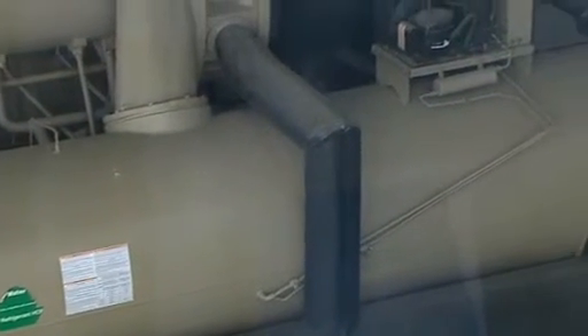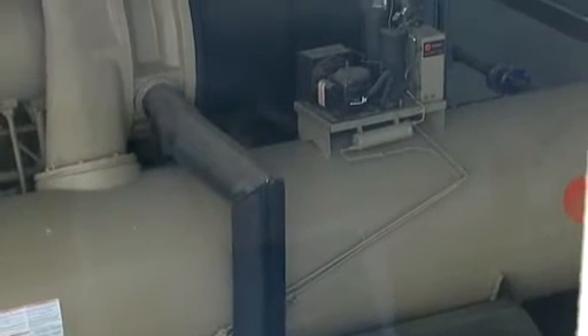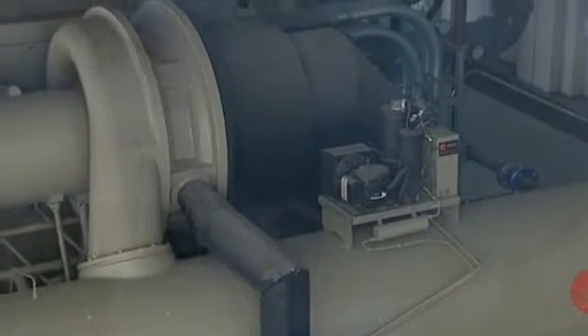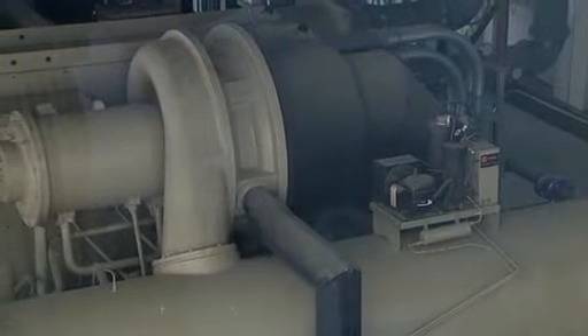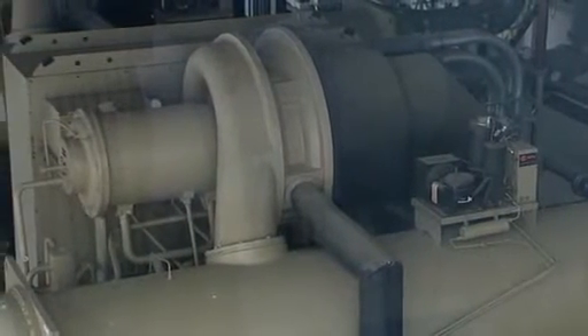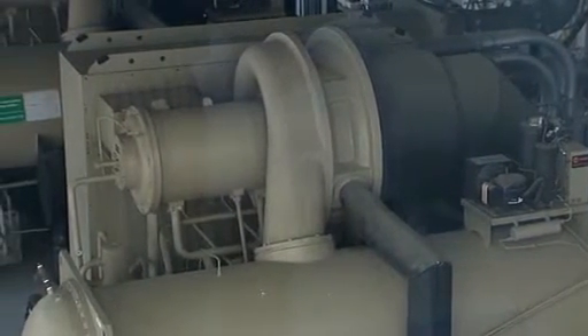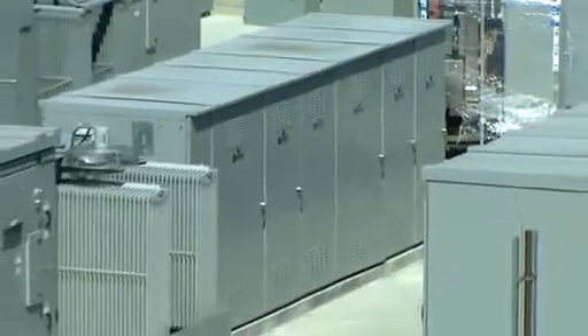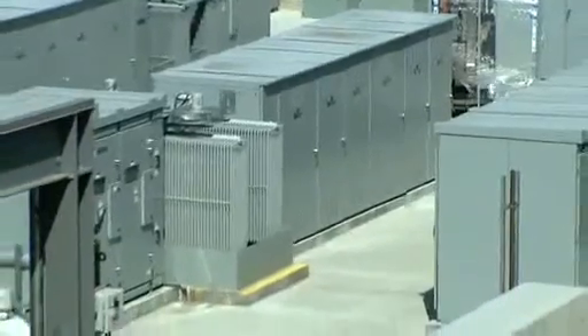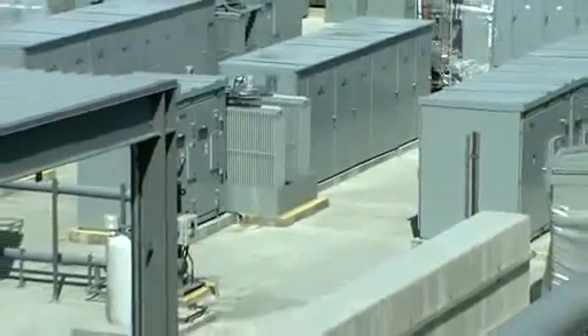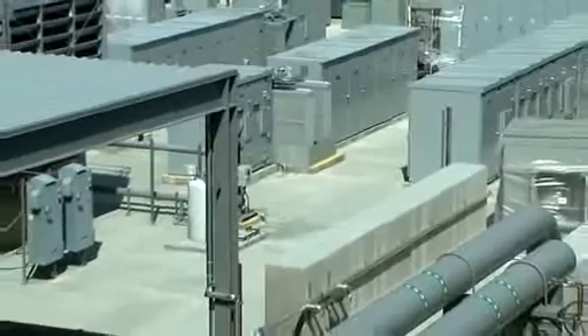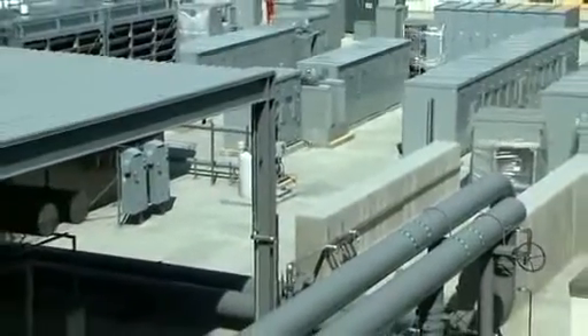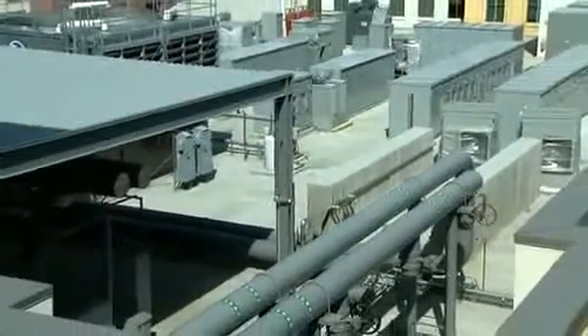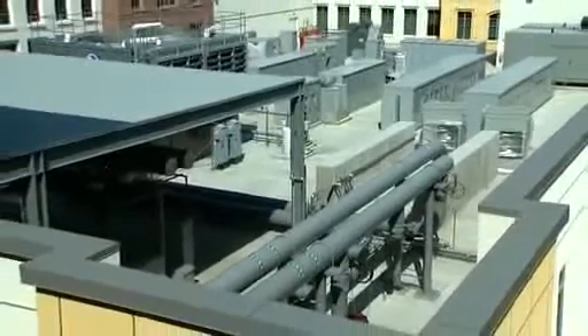The fact that we now can continue to grow with that and keep our PUE of 1.28 is critical, because we are at lower densities today, but as we scale up, our PUE will stay constant. So our data center starts at 9 megawatts, scales to 16, and then scales to 21. And if you look at the yard itself, I can now snap in chillers, transformers, and double my power. I can do chiller towers, generators, pumps, everything I need to expand with no major construction.